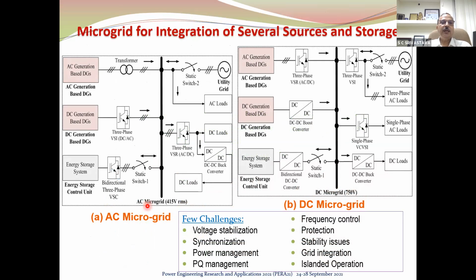Now this is the structure showing the AC microgrid, where all sources, storage, and loads connect at an AC bus, and the DC microgrid. One thing should be very clear: in a DC microgrid, the voltage becomes very important. Here you have a very standard voltage, but DC microgrid voltages are still evolving. There are a few voltages, like 48 volt, 72 volt, 24 volt, which have been adopted in India. Why have they been adopted? Because the safety problem is not there at these smaller voltages, so even if you touch it, nothing happens. But don't try to touch it.